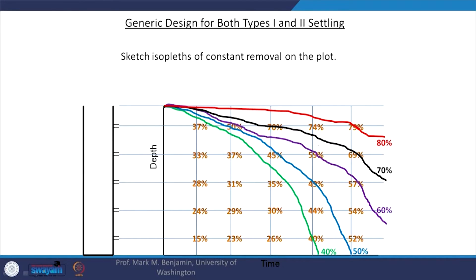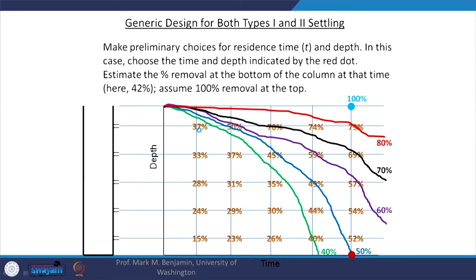We got data, plotted the percentages, and from those percentage removals we can get what are called isopleths — lines of constant removal, such as 30, 40, 50, 60, 70, 80 percent. These are obtained by interpolating data measured at different depths. To use this, we choose a particular time and depth — the x-axis is time.